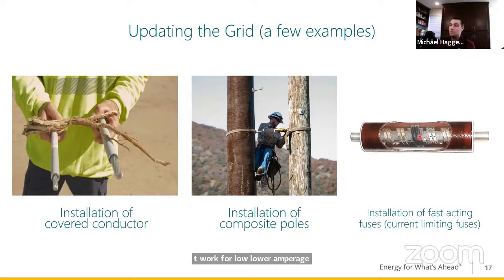These are really cool - when they see a fault and too much current, these metal bits actually melt, and there's sand inside, so they melt the sand and it turns to glass. Glass is an insulator, so the electricity doesn't flow through the fuses anymore.